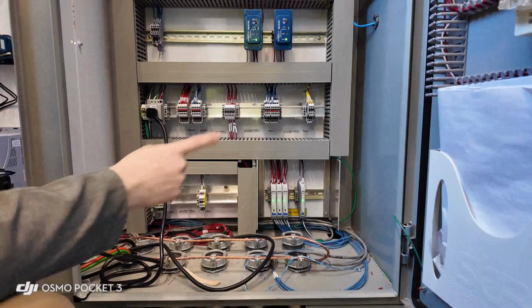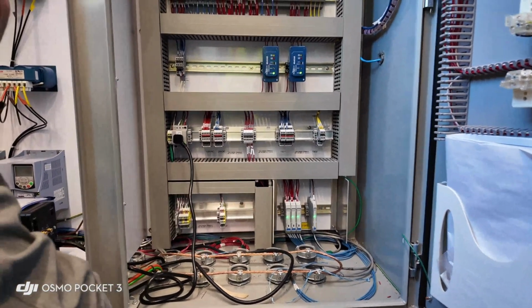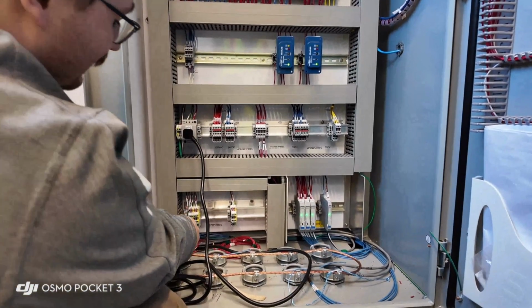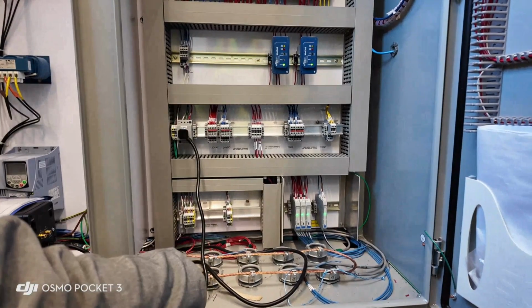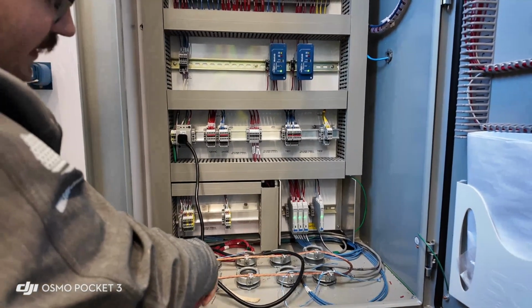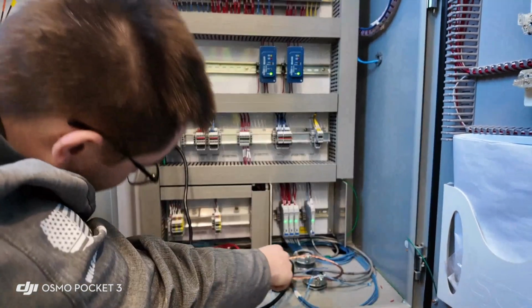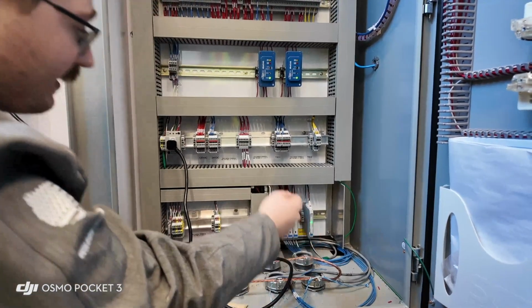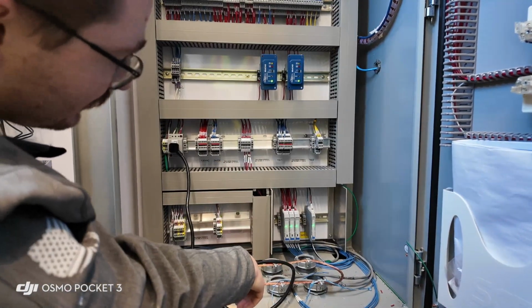Since it's out in the well, if there's a lightning strike or anything like that, the surge protection device is going to prevent anything from going up to your controller. And then this is just spare TBA2 terminal blocks, which is your analog outputs. Down here is your intrinsically safe relays area.